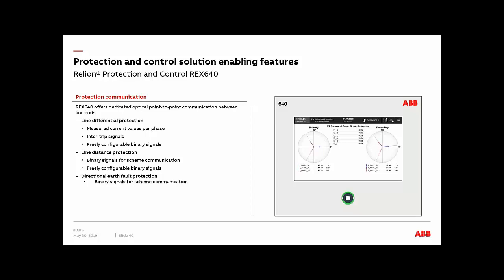So we'll give you measured current values per phase. You can send inter-trip signals, and you have, as we mentioned before, 16 binary signals that you can share between the two line ends through this dedicated communication channel. For the line distance protection as well, you still get your same 16 configurable binary signals, or you can use your different transfer trip schemes depending on your specific application.